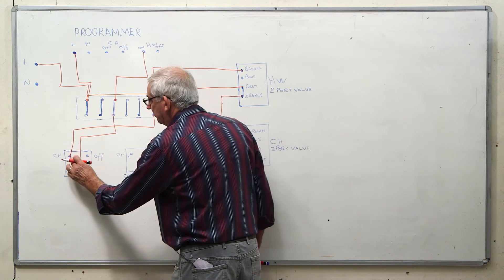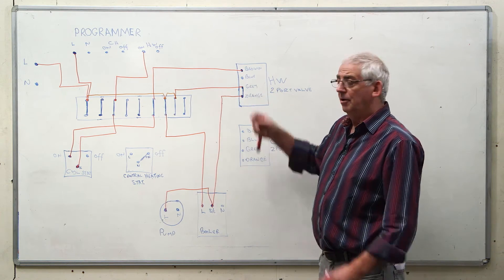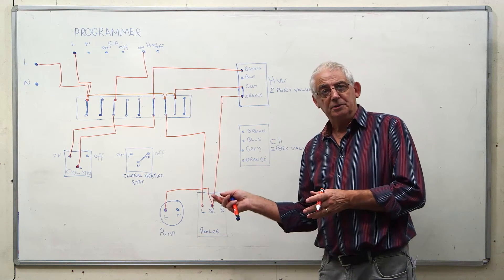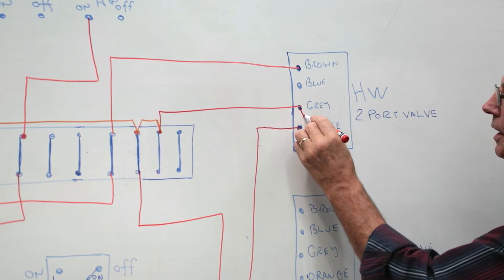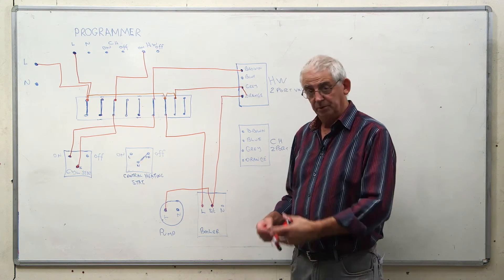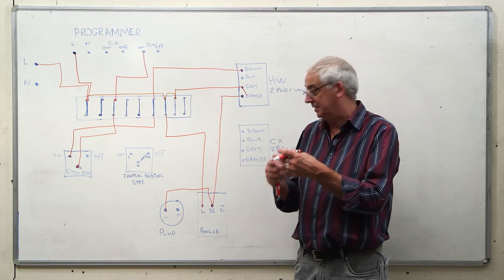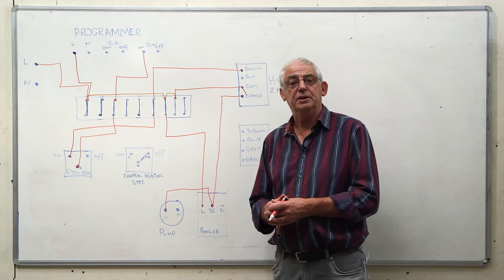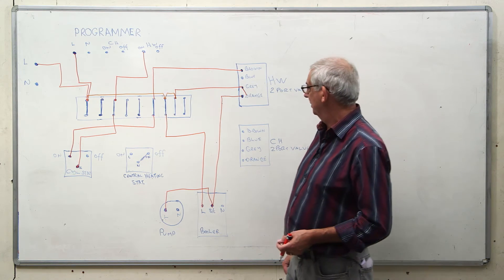Of course, if I turn this off, the valve now, because it's spring loaded, goes back to its closed position which would then open the micro switch. The signal to the boiler would stop because there's a permanent live. If it was needed to, this pump would continue but that is an electronic device within the boiler which we don't generally need to worry about.